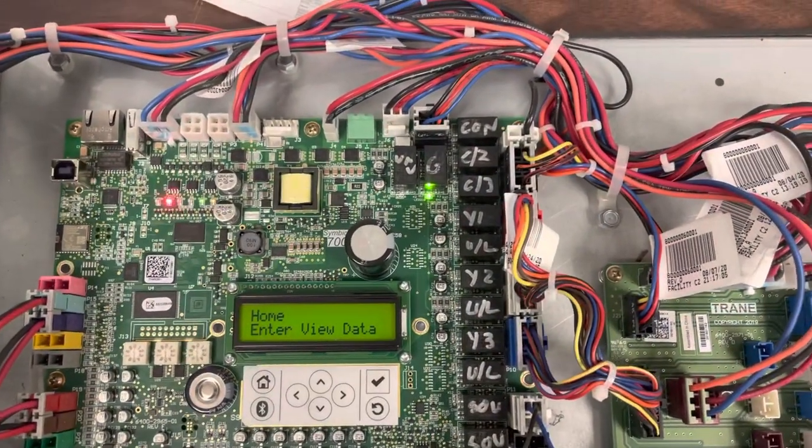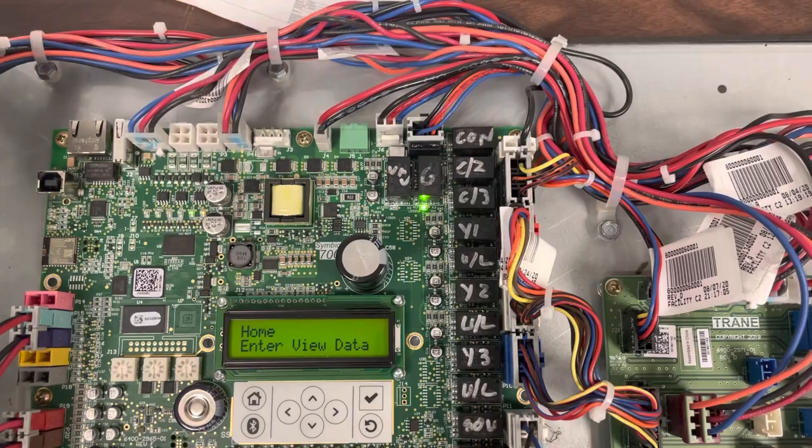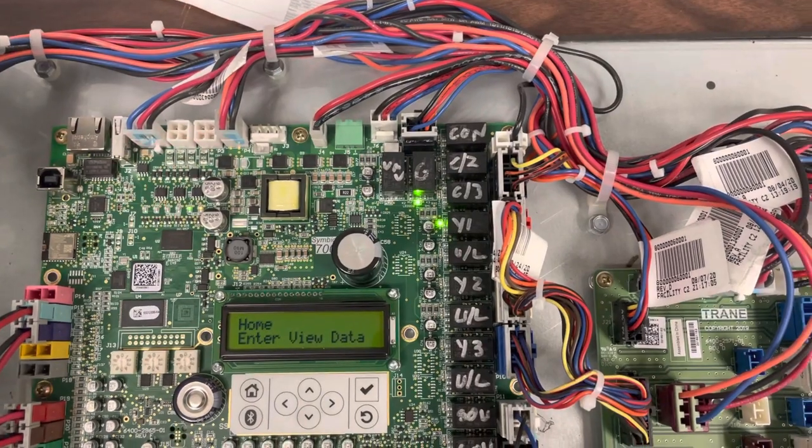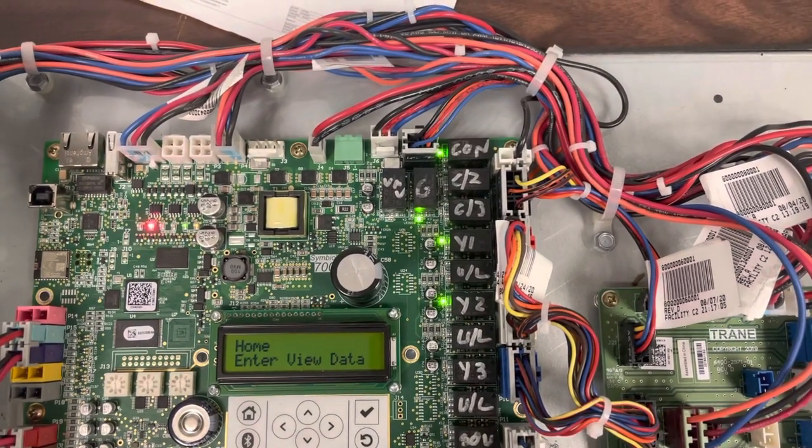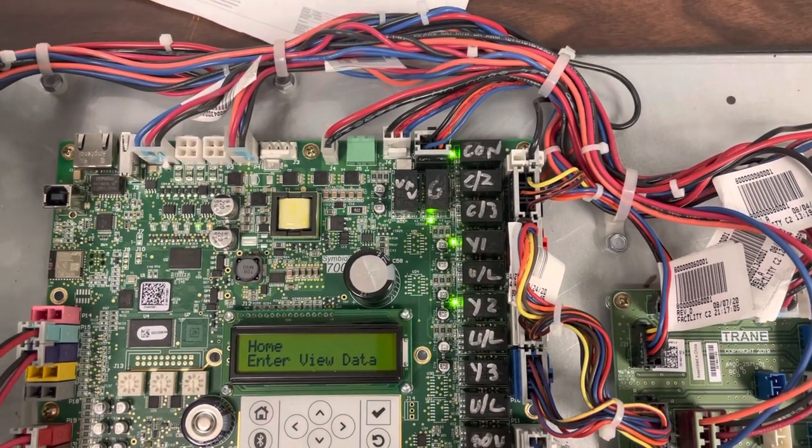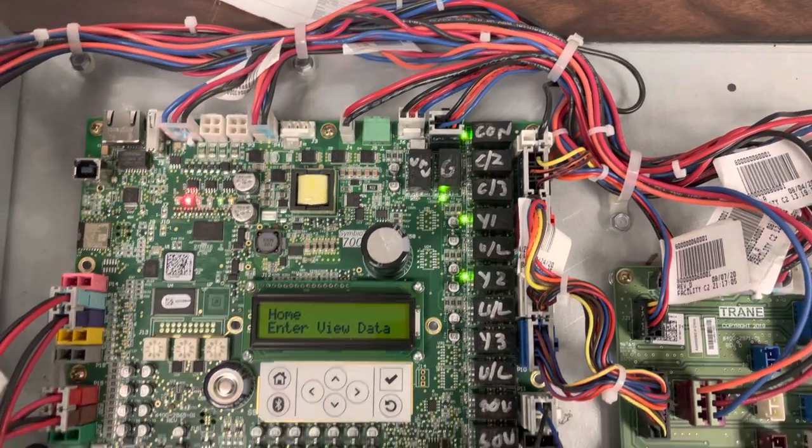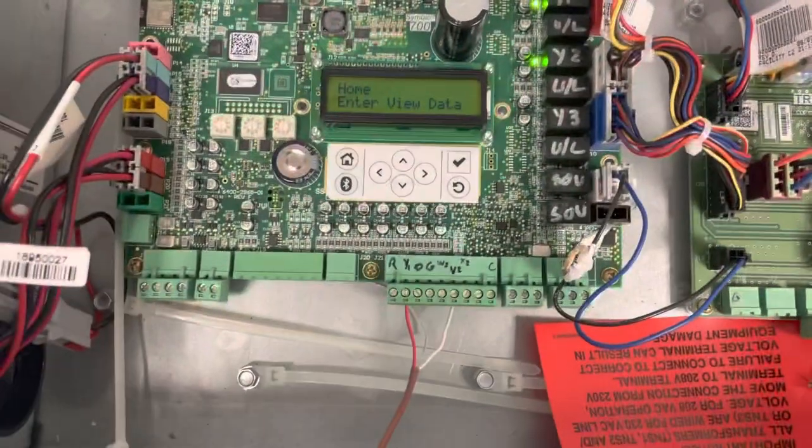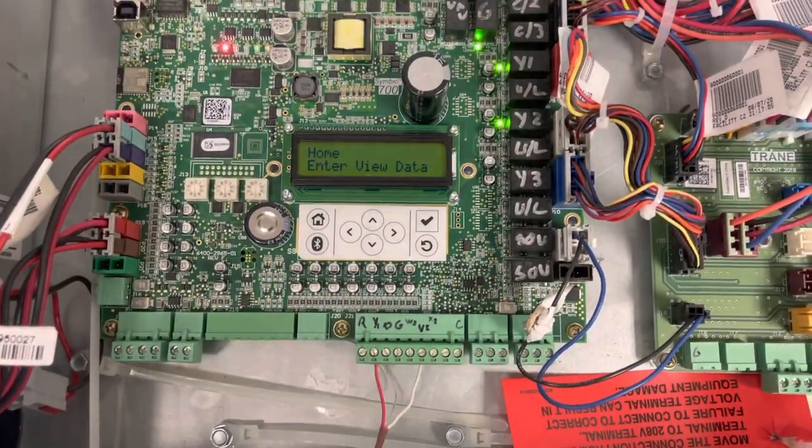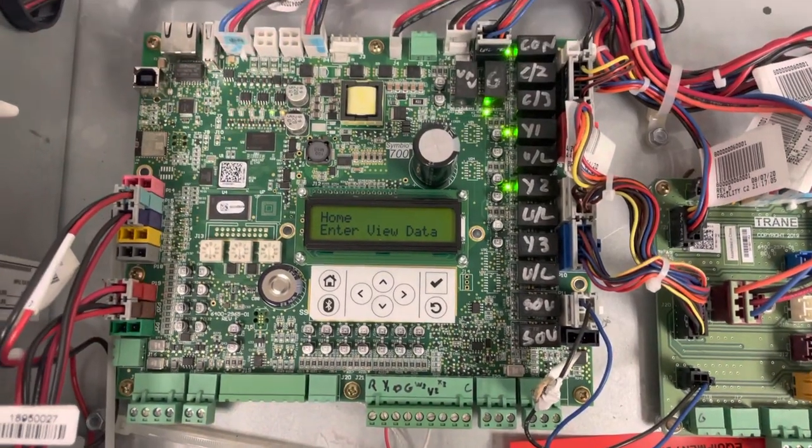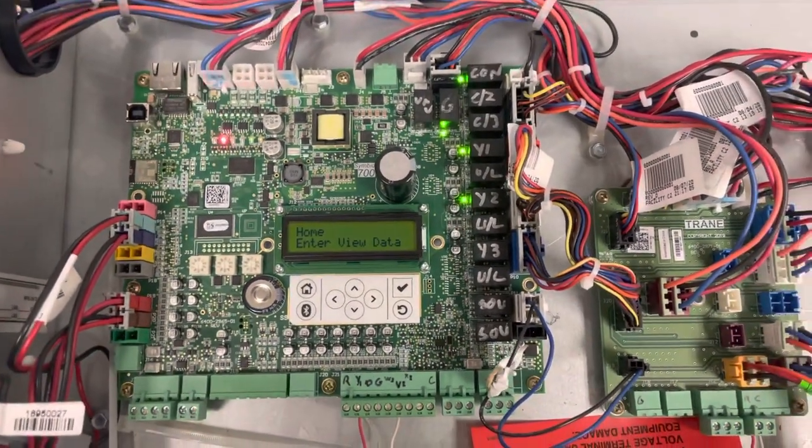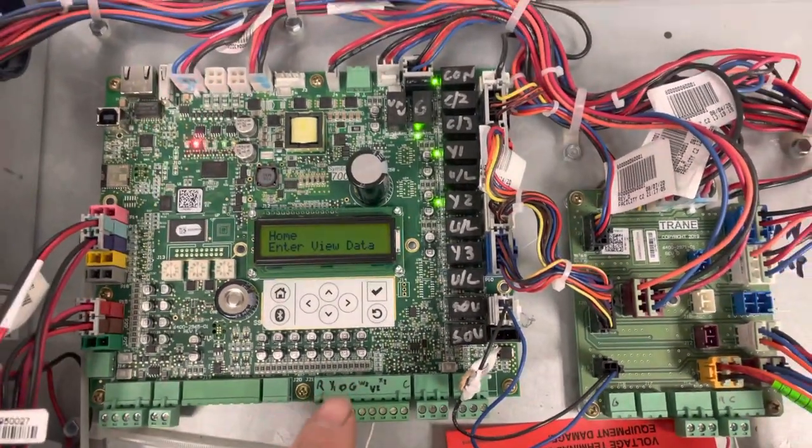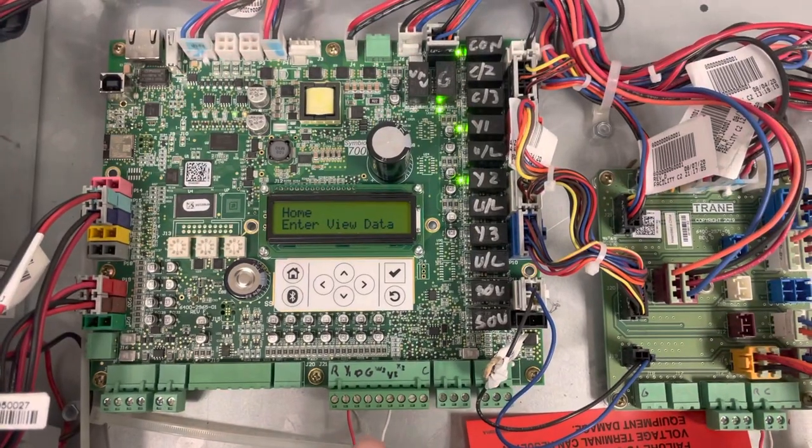Blower's energized. Now this is going to take me a little bit, no time delay. So there you go, Y1, Y2, condenser fan. So if I had high voltage going to this and the blower or the fan motors and the compressor, we'd be spinning off right now. So just by these two wires, it's sending the input into my Y1, Y2 call.